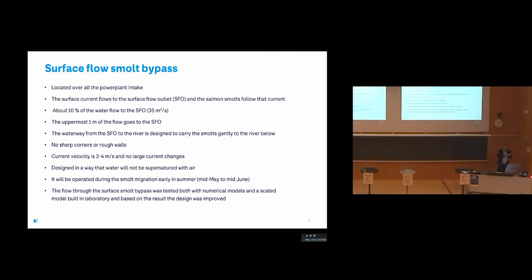The surface flow smolt bypass is located above the power plant intake. It takes the uppermost one meter of the water and 10% of the flow goes through the bypass. The waterway from the intake of the smolt bypass is designed to carry the smolts gently to the river below. There are no sharp corners. The current velocity is 2 to 4 meters per second and there are no large or sudden current changes.